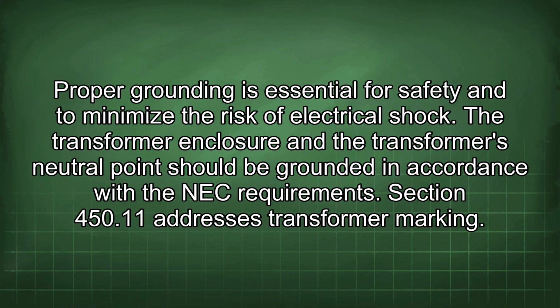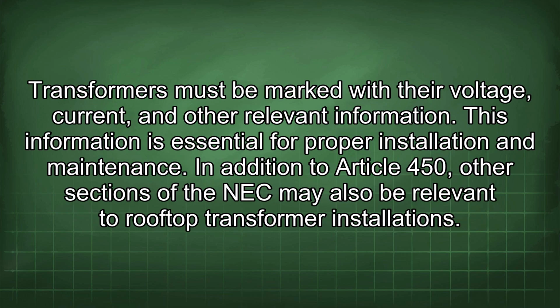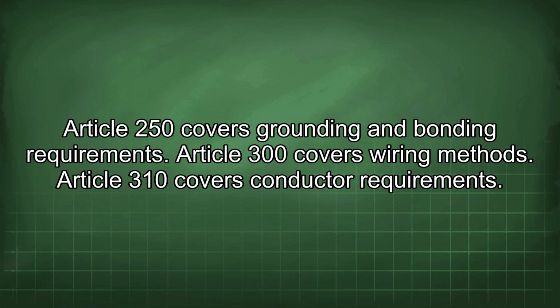Section 450.11 addresses transformer marking. Transformers must be marked with their voltage, current, and other relevant information. This information is essential for proper installation and maintenance. In addition to Article 450, other sections of the NEC may also be relevant to rooftop transformer installations. Article 250 covers grounding and bonding requirements.